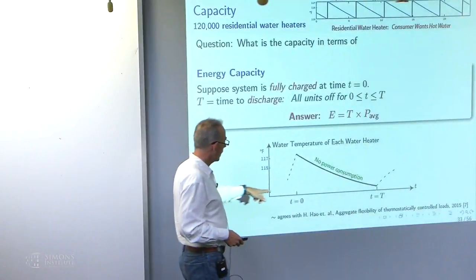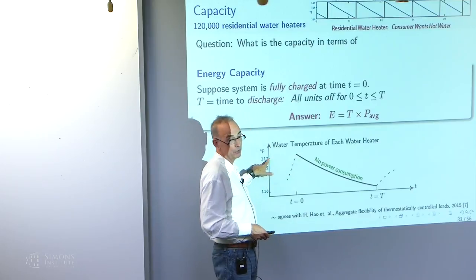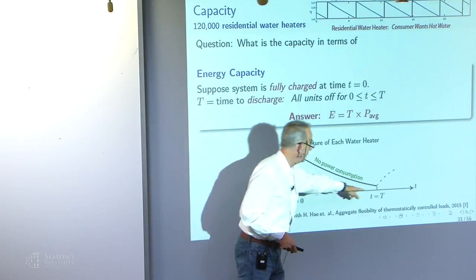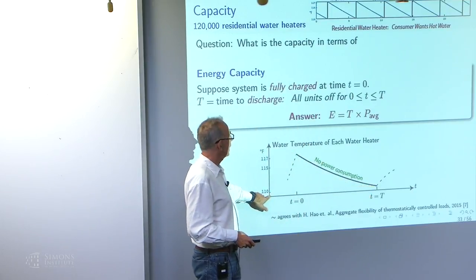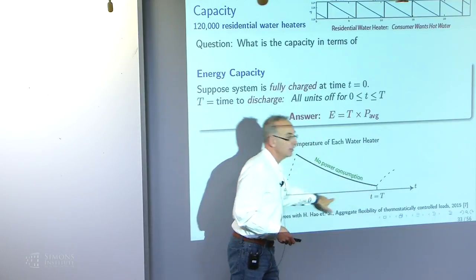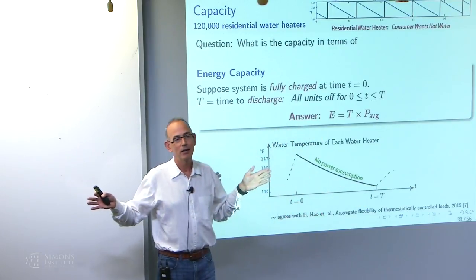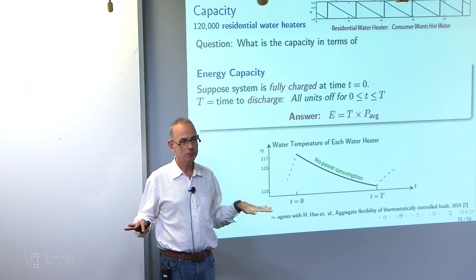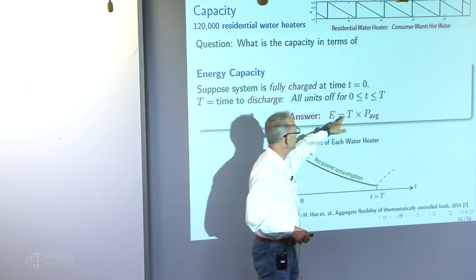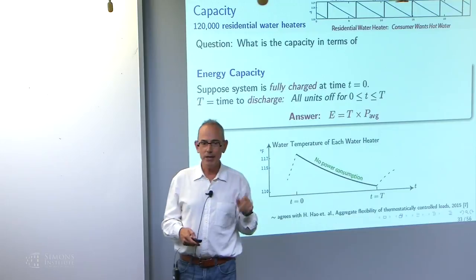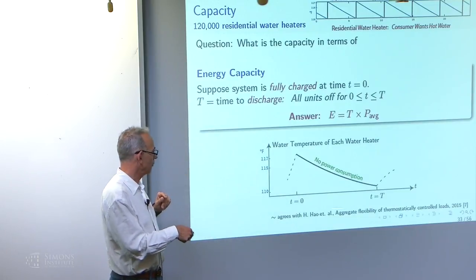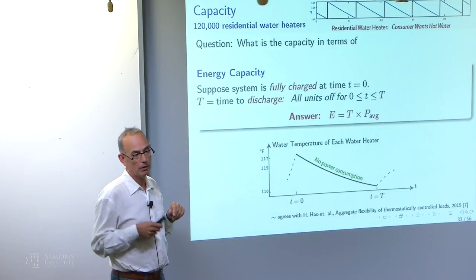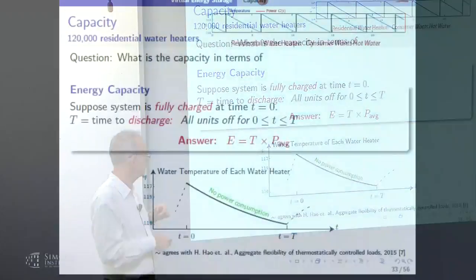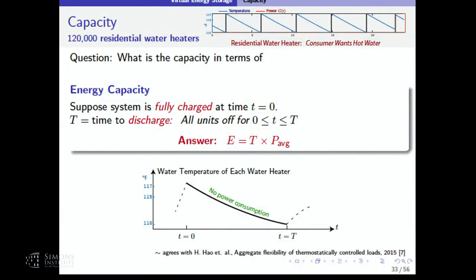At time zero, I had them all at the highest temperature. I pulled the plug and waited until it got to the lowest temperature. That time tells me how long it takes to go from 30 megawatts to zero. Multiply time times average power, and that's energy. What's amazing is it agrees almost exactly with the formula derived using different methods, from a paper by Kamishwar and colleagues, who helped with this. So energy is time times power, and the time constants of the unit tell us this.